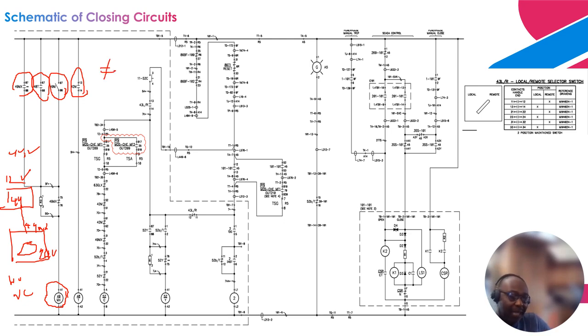And that should be able to energize the coil for this relay. In series with this normally closed contact, in normal operation, it's a self-state, normally closed contact. So once any of these contacts changes state from normally open to normally closed, or you close the switch, and that is in series with this, that should give the permission to be able to energize this 49MX coil and that auxiliary relay as such.